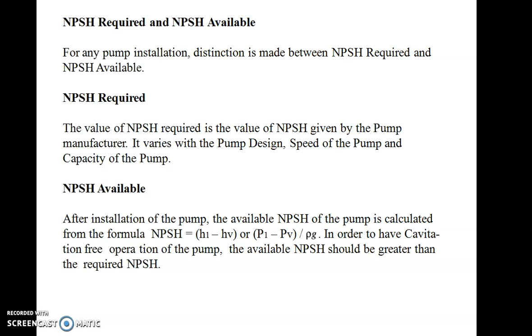So NPSH available is the customer requirement, and NPSH required is the supplier requirement. Generally in most cases your NPSH available is well above the NPSH required, and that's why there is no problem. Suppliers take care that NPSH required comes out less than NPSH available.